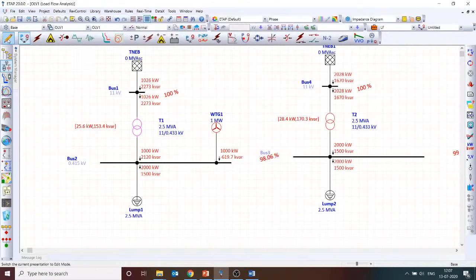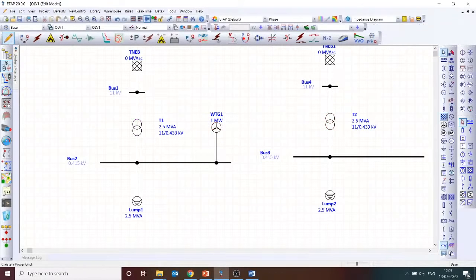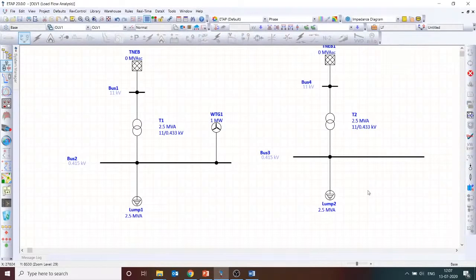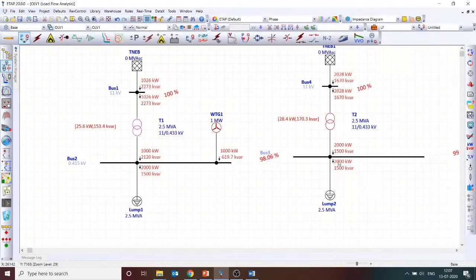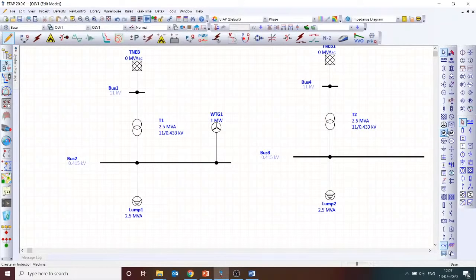Okay. So this is not a real scenario. Let's go to the real scenario. Even if I run a load flow here, the industry will not run with this scenario. I mean, 2.5 MVA at 0.8 power factor, and they will not pay a penalty for the poor power factor. What they will do, they will put up a capacitor bank, to ensure the power factor is maintained above 0.9 per unit.